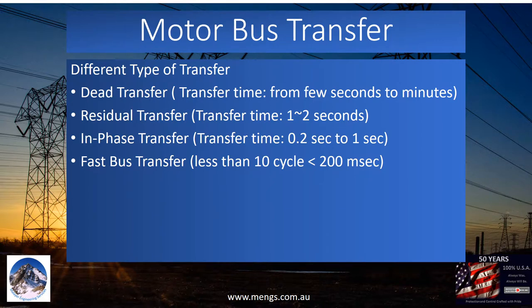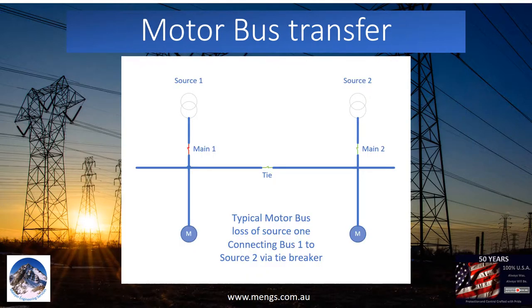Depending on transfer time, we can have four types of transfer. Dead transfer: the transfer time is about a few seconds to minutes. Residual transfer: the transfer time is about 1 to 2 seconds. In-phase transfer: the transfer time is about 200 milliseconds to 1 second. Fast transfer: the transfer time is less than 10 cycles, or 200 milliseconds for a 50 Hz system. Depending on type of transfer, closing the tie breaker can happen in a few cycles for fast transfer, to a few minutes for dead transfer.